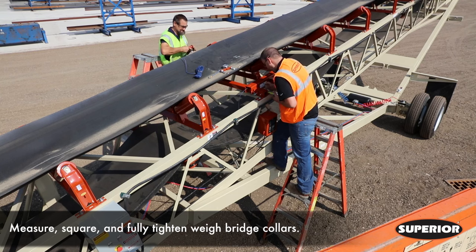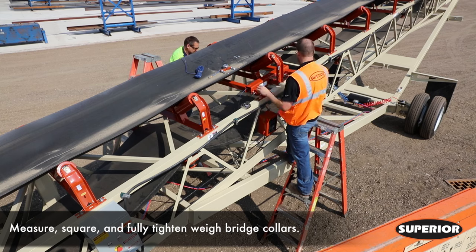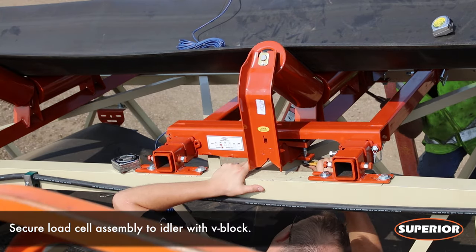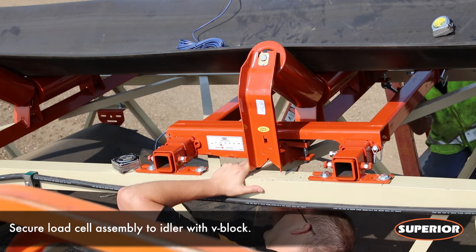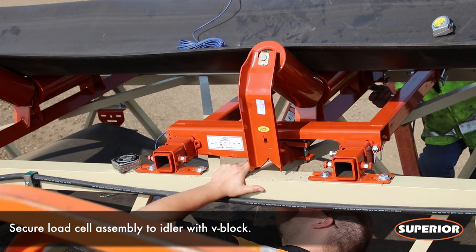Measure and square the weigh bridge. Once square, tighten locking collars to prevent the weigh bridge from shifting or sliding. Using V-blocks, secure the load cell assembly to the idler with appropriate equipment. Use care not to over-tighten the V-blocks, as this will twist the load cells, giving false readings.